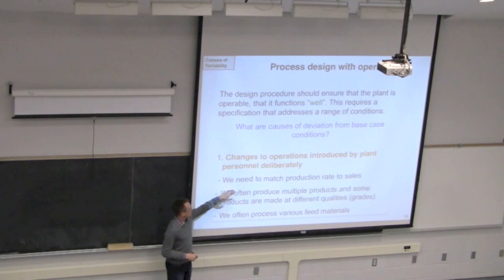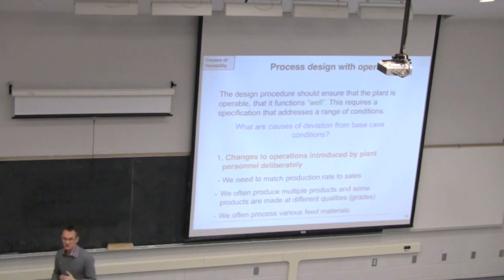Think of the case when you also go increase your rate. Now it's the opposite. You may need extra cooling or extra heating. So we don't design just for the base case rate of sales. We design for 25% more or 50% greater level of sales, and so then our heat exchangers need to be sized larger as well for those types of situations.